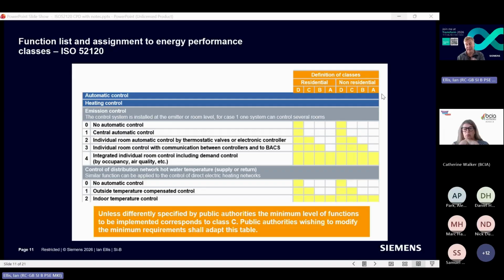If you've done a design to Class A and someone says they can't afford it and want to value engineer it down, for example by removing the CO2 sensors from meeting rooms, you can point out there's a cost to that: more cabling required back to the BMS, more engineering at the BMS level, and so on. You can say that's fine, you can do that, but here are the effects it will have on the running costs of your building. So it's a way of helping them decide whether they really want to value engineer this job.